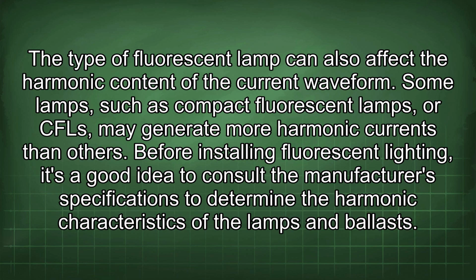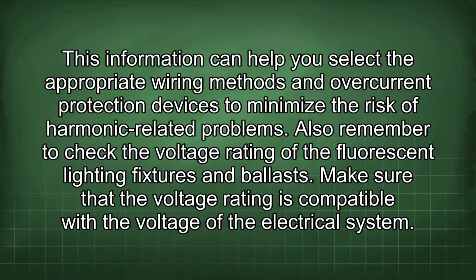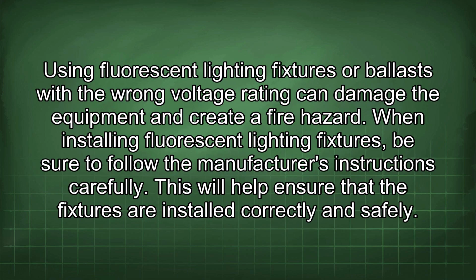Before installing fluorescent lighting, it's a good idea to consult the manufacturer's specifications to determine the harmonic characteristics of the lamps and ballasts. This information can help you select the appropriate wiring methods and overcurrent protection devices to minimize the risk of harmonic-related problems. Also remember to check the voltage rating of the fluorescent lighting fixtures and ballasts. Make sure that the voltage rating is compatible with the voltage of the electrical system. Using fluorescent lighting fixtures or ballasts with the wrong voltage rating can damage the equipment and create a fire hazard.